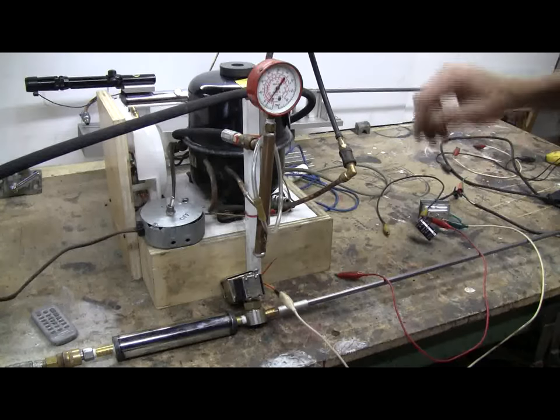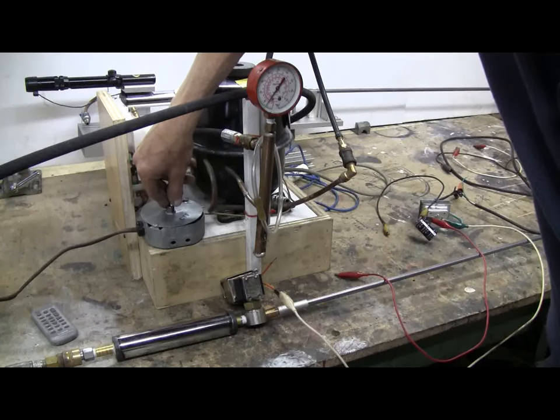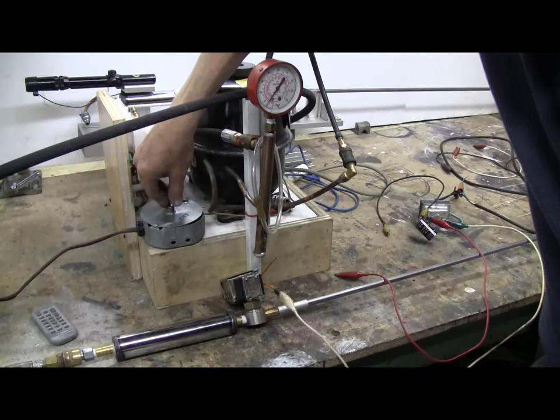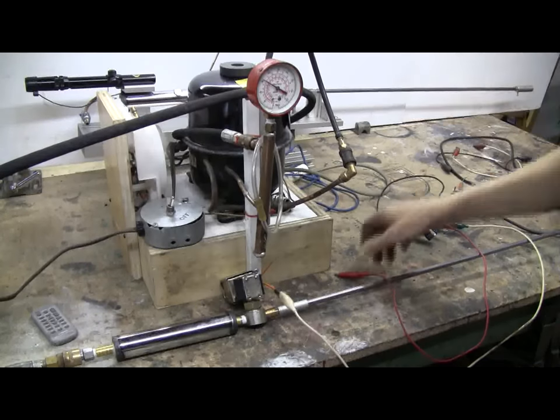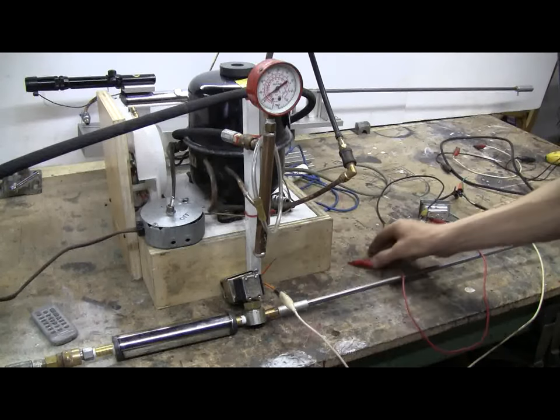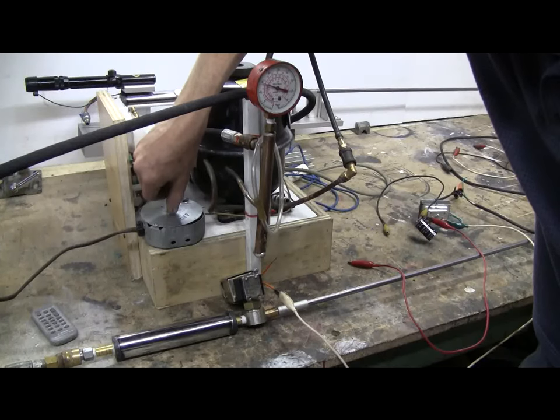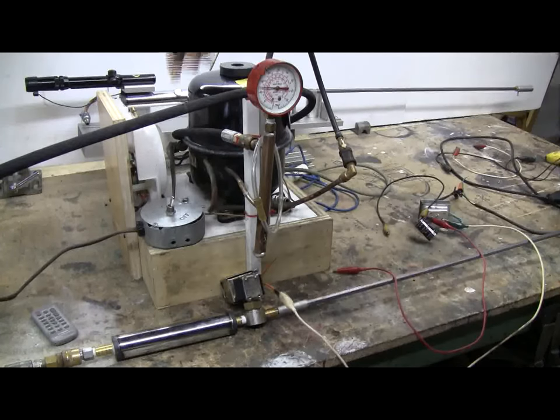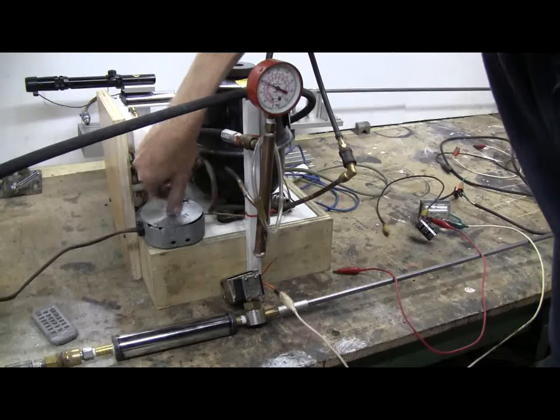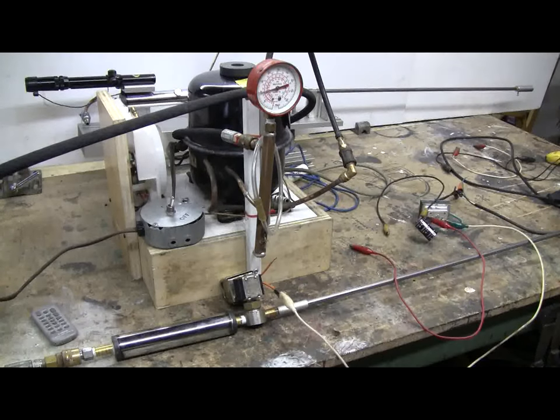Let's move on up to 150 psi and again attempt to trigger the valve using 24 volts AC. 150 psi, let's do it again. Gauge is past 150, fire. And a third time, 150, fire. Seems quite reliable so far.